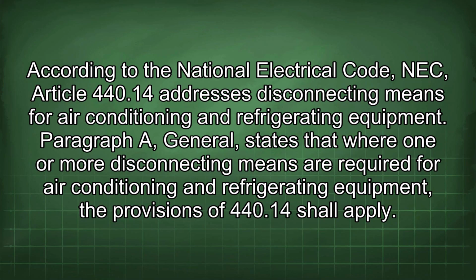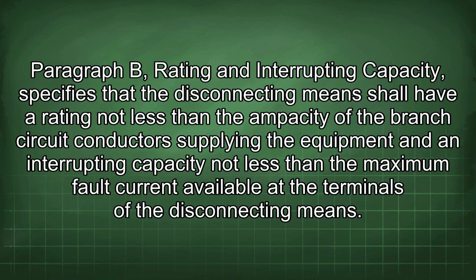According to the National Electrical Code, NEC, Article 440.14 addresses disconnecting means for air conditioning and refrigerating equipment. Paragraph A, General, states that where one or more disconnecting means are required for air conditioning and refrigerating equipment, the provisions of 440.14 shall apply. Paragraph B, Rating and interrupting capacity, specifies that the disconnecting means shall have a rating not less than the ampacity of the branch circuit conductor supplying the equipment and an interrupting capacity not less than the maximum fault current available at the terminals of the disconnecting means.